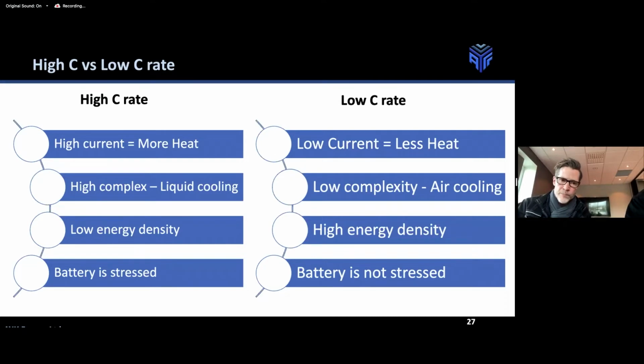In a high C rate application, because of the heat, you're going to need liquid cooling, and that adds complexity to a system. With a low C rate, you can normally get by with just air cooling, which is perfectly adequate. Because of that added complexity with liquid cooling, you're going to have a lower energy density. So for the same kilowatt-hour battery, a high C rate system is going to be heavier, while a lower C rate system has a higher energy density.